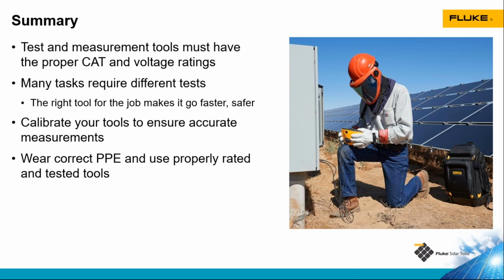And finally, something that we haven't really talked about but is really important is wearing the proper personal protective equipment. The person in this picture is doing some testing with the SMFT 1000 in a commercial combiner box. They have an arc flash face shield with balaclava, fire rated clothing, electrically insulated gloves. They've got all the right equipment on. The only thing they're doing wrong is kneeling on the ground. That's not a best practice because it makes a much lower resistance connection to the ground, so it's easier to get shocked or electrocuted. So either standing on both feet or putting down an electrically rated rubber mat would be preferred. But other than that, they're doing a really good job.